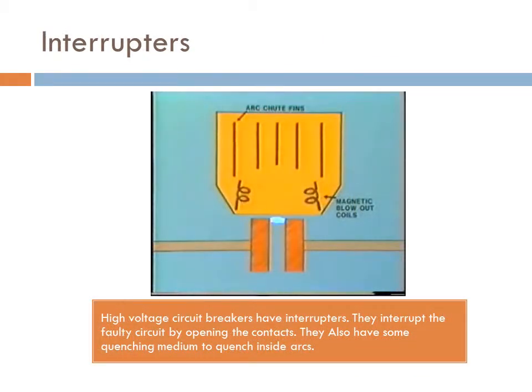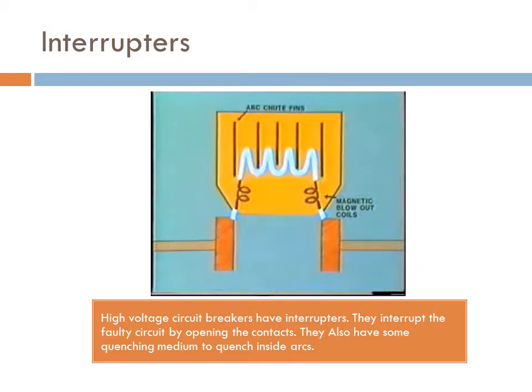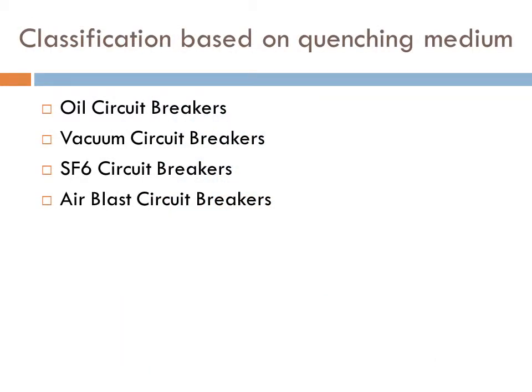High voltage circuit breakers have interrupters. They interrupt the faulty circuit by opening the contact. When a very large amount of current flows through the circuit, both the contacts are separated and produce a very large arc. This arc is quenched by some quenching medium. Circuit breakers can also be classified based on the quenching mediums. These circuit breakers are oil circuit breakers, vacuum circuit breakers, sulfur hexafluoride circuit breakers, air blast circuit breakers, using oil, vacuum, sulfur hexafluoride, and air blast as a quenching medium respectively.